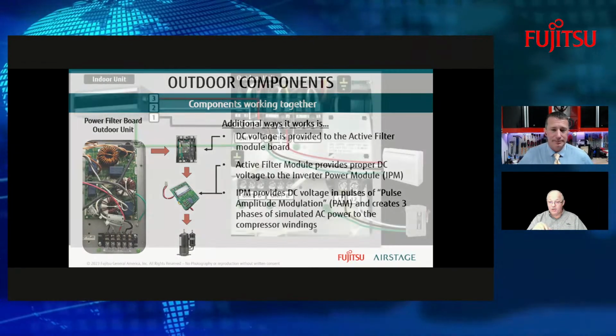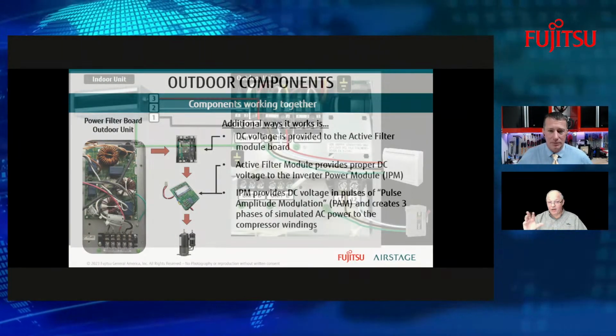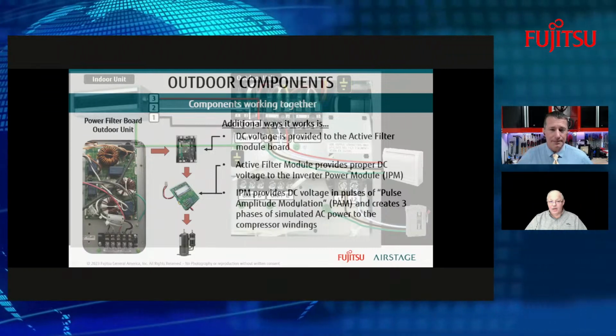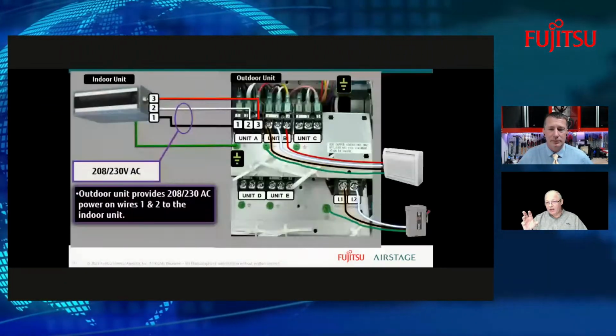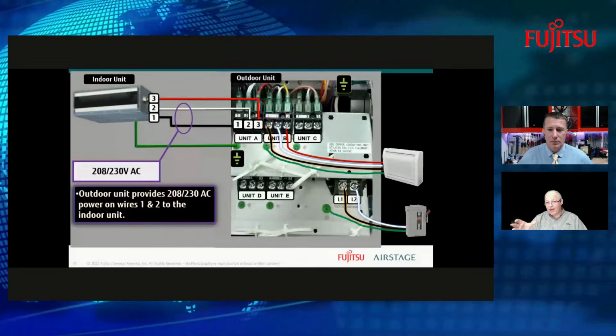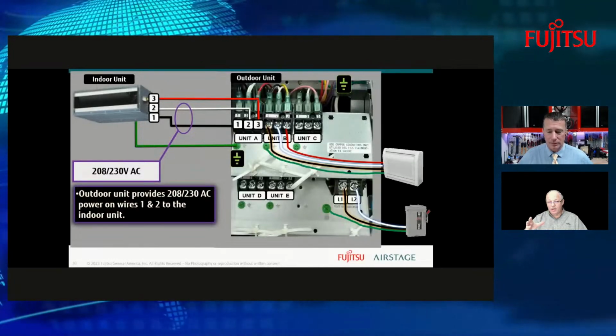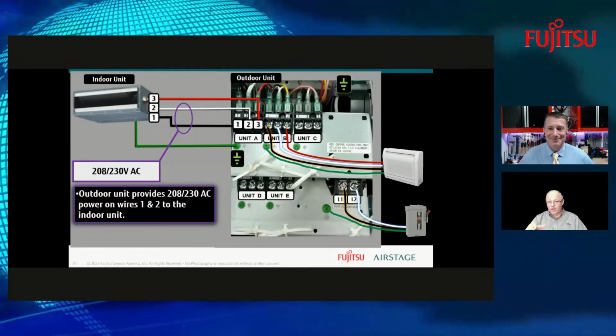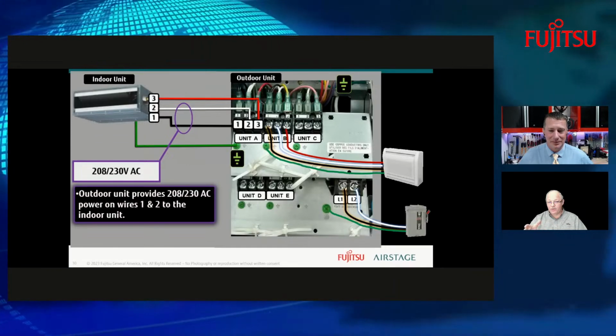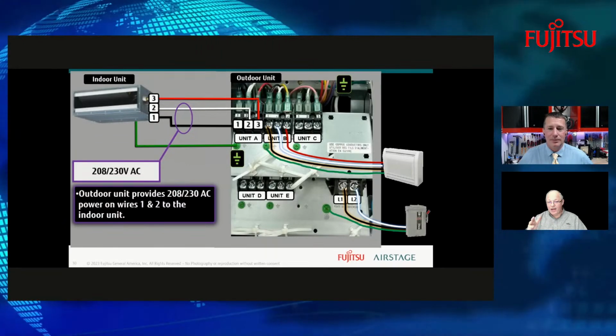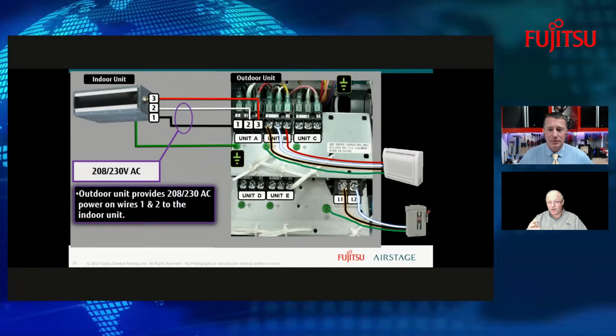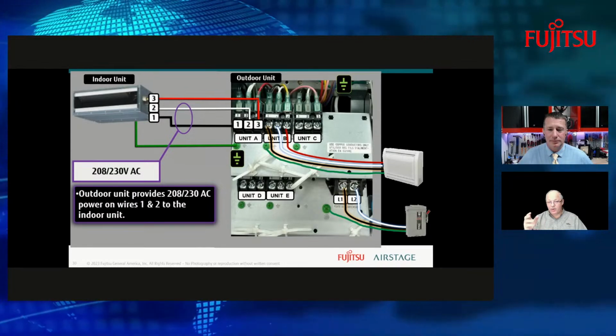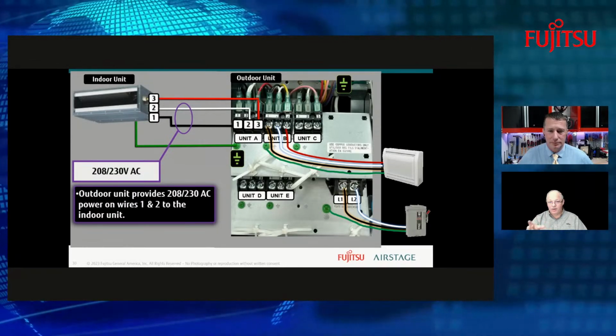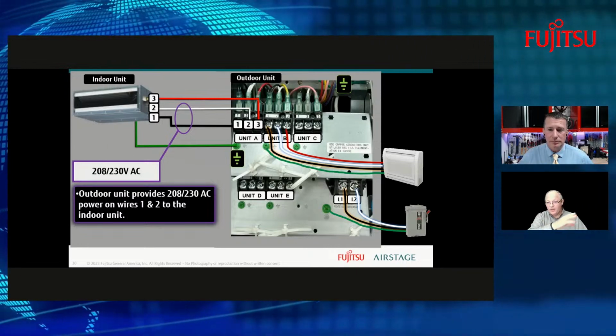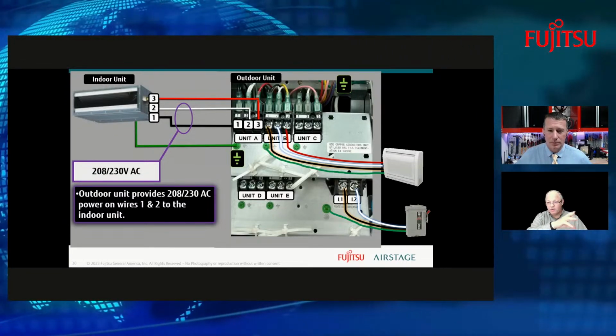Oh, so you should see the voltage varying on that compressor. Okay. Now, let's take a look at how the voltage moves from the outdoor unit to the indoor unit. Yeah. So here on lines 1 and 2, we have the 208, 230 volt. And that's where your power is going to go to the indoor unit. Now, the indoor unit is going to, at its board, take that information and then tell that motor what it needs to do on speed.